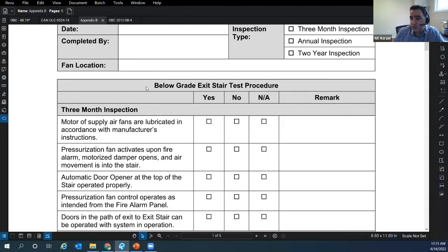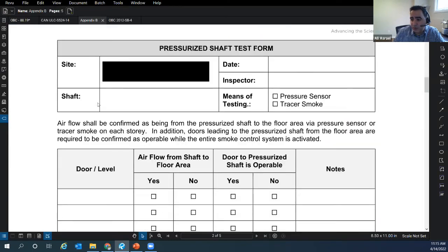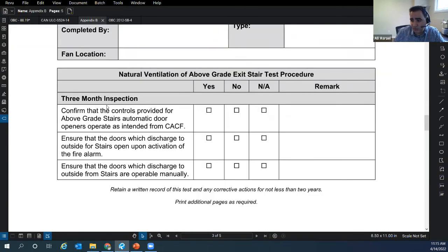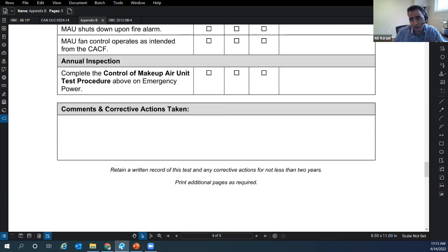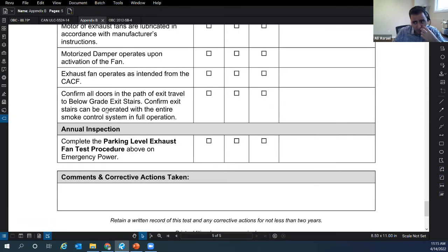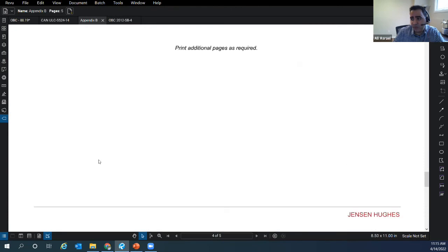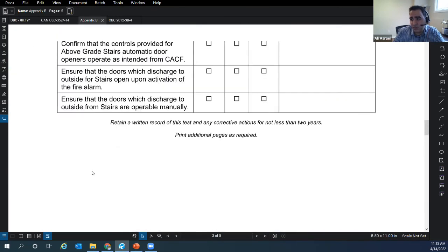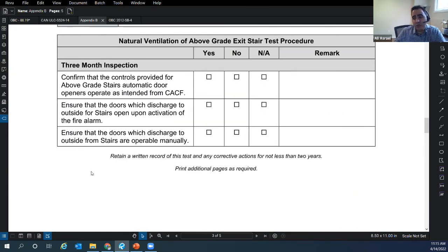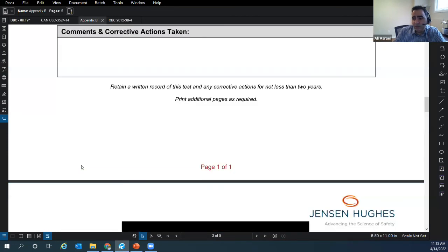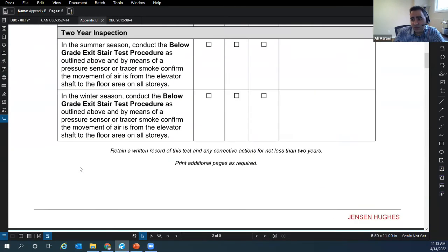The report that I showed you is part of the annual inspection. So you have your basically 3 month tests, and when it comes to the annual inspection of the shaft, you have to do it on emergency power. Basically, you're following the same procedure as every 3 months, but then you complete the parking level exhaust fan test procedure above on emergency power. This is for the parking fan, but for any fans, basically anything that you're doing every 3 months, when it comes to the annual inspection you have to do it on emergency power, and that's coming from the National Fire Code.